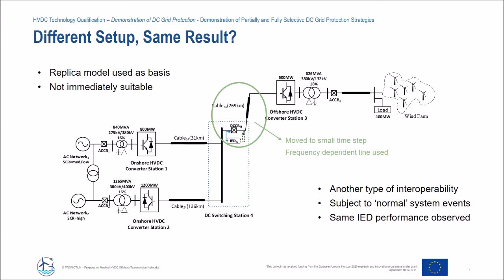We're combining the physical IEDs with physical control hardware. Important to point out, we didn't actually change anything in the control hardware of the link, so everything we observed could possibly be improved upon. But it's also reassuring to know that with an existing system design, we managed to get the IED to perform similar to the testing with the generic models, and we could continue point-to-point operation for a fault on the third line based on this protection scheme integrating without any additional works on the controls. So it just goes to prove that the protection system design is adequate for a current scheme and could readily be introduced.